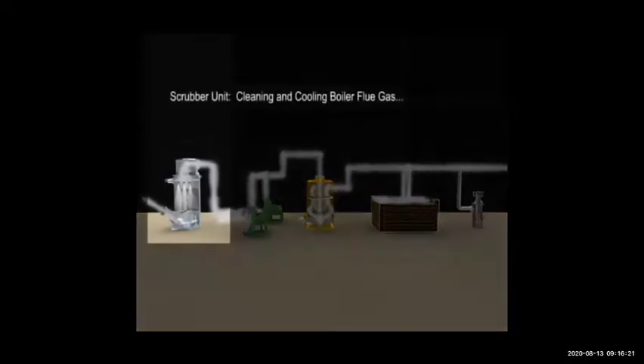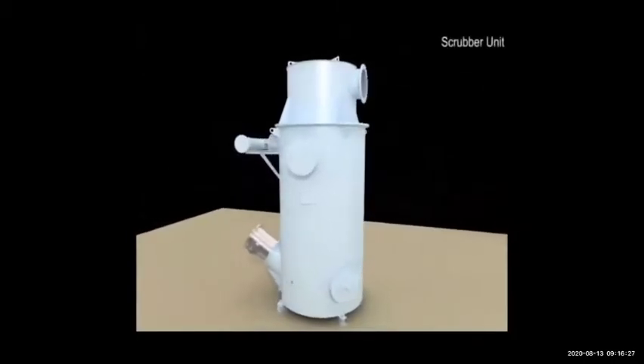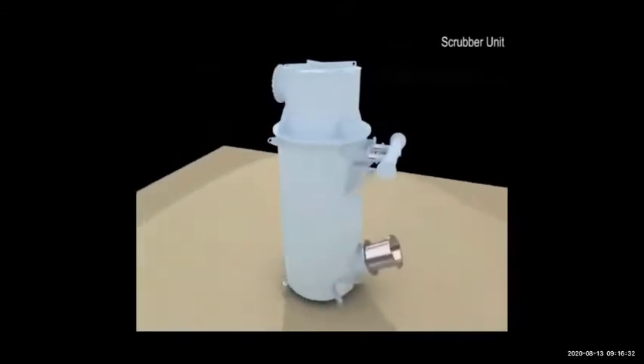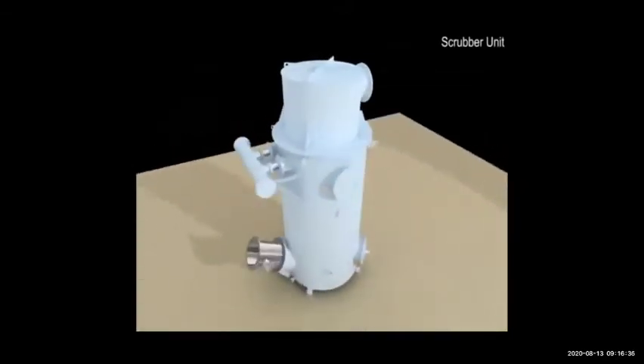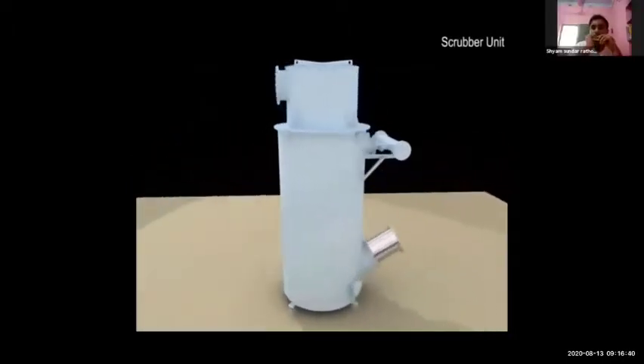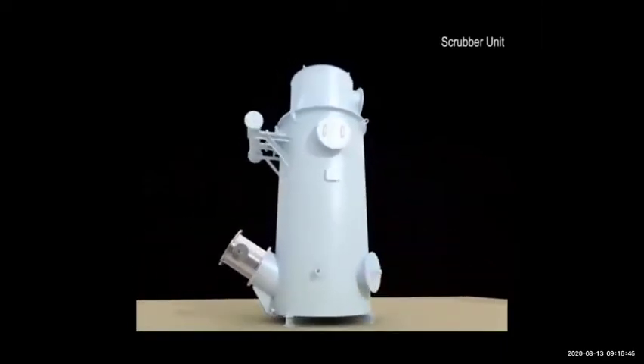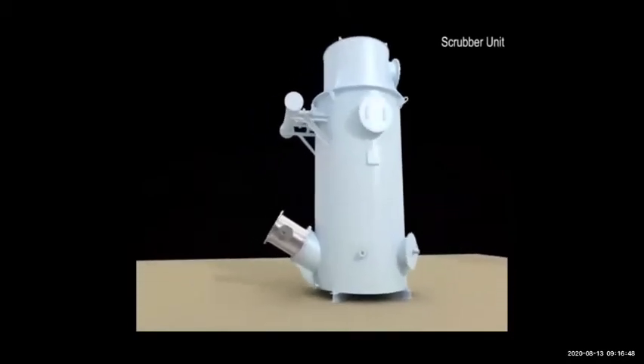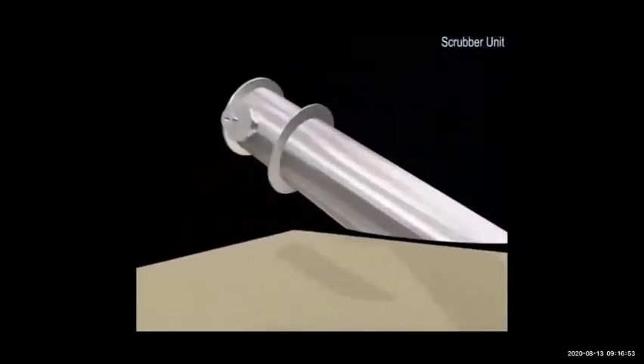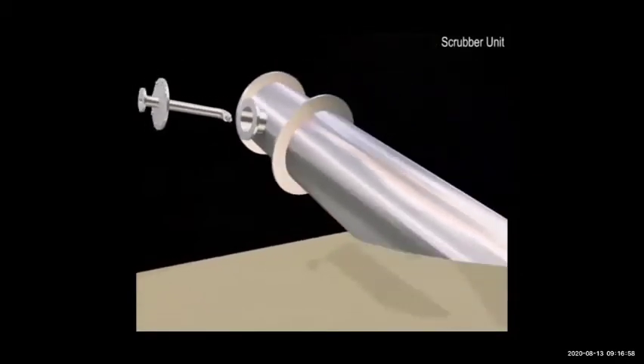Let's start understanding each part one by one. The first is the scrubber unit. The main use of the scrubber unit is to clean the gas — inert gas — because it is coming from burning fuel in the boiler and there will be a lot of impurities like carbon, sulfur, and other dust particles. The scrubber has two main functions: one is cooling down, one is cleaning.